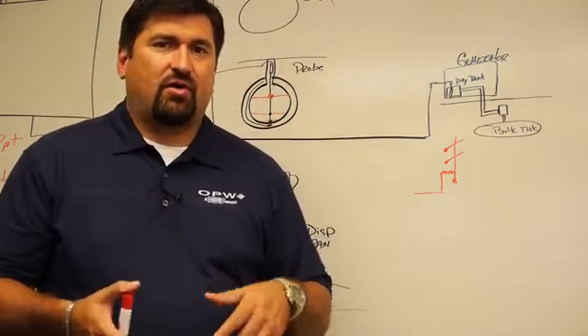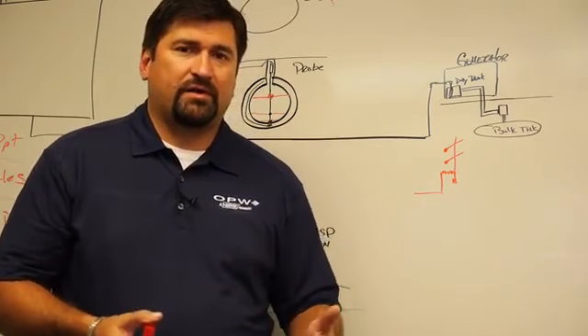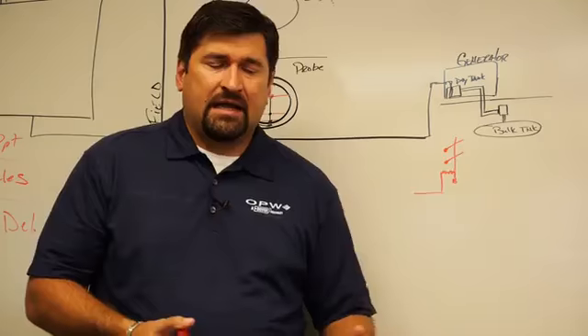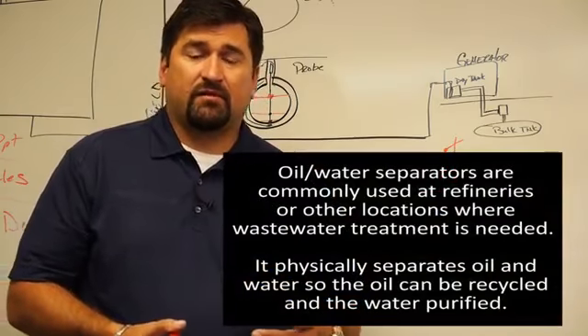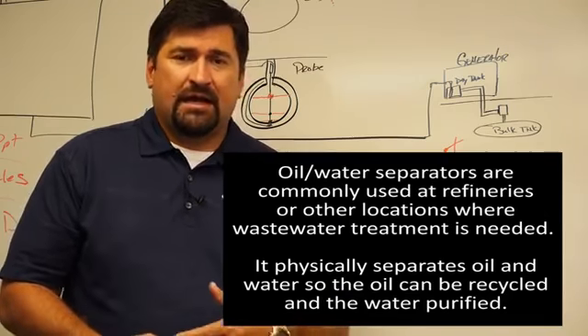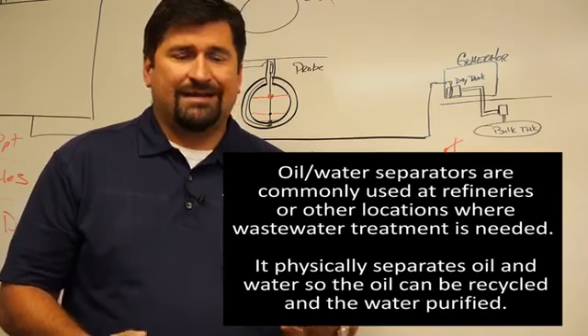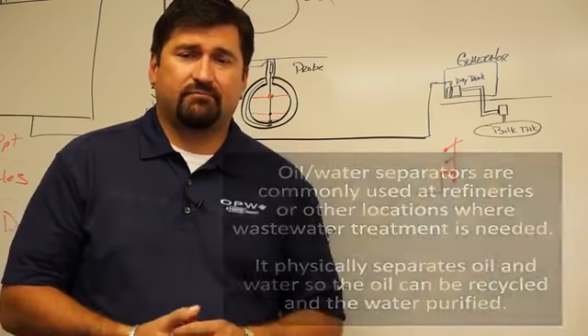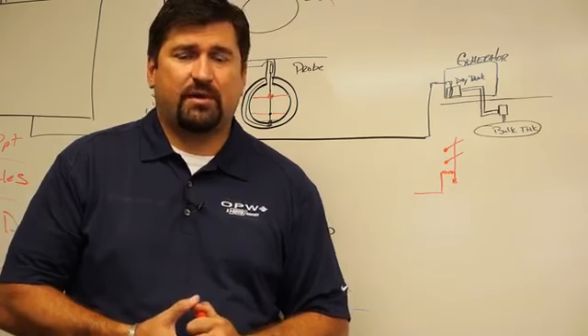Another application is an oil water separator, where you can put a probe into an oil water separator tank, and the gauge is actually capable of distinguishing between the water and the waste oil that's in that oil water separator. At the point in which the level gets too high, you can set off an external horn, and that would alert somebody or send somebody an email saying that it's time to come out with a vac truck and clean out the oil water separator.